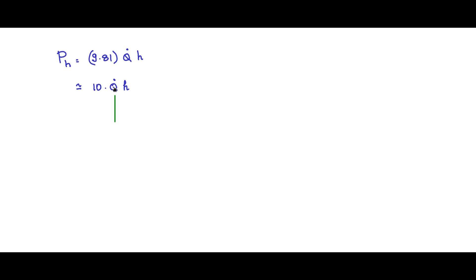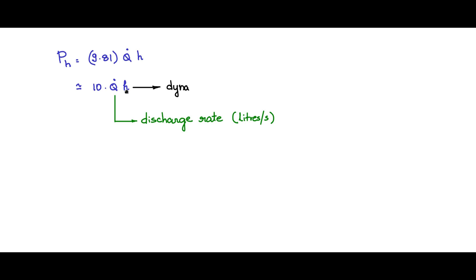The discharge rate or flow rate q̇ is obtained from the application — specifically, how many liters of water you need to transfer from the lower level to the higher level, or how many liters are required for irrigating a given piece of land. This value comes from the user requirement. H is the total dynamic head in meters, which is a combination of the suction head, the discharge or delivery head, and an equivalent head representing friction losses in the pipe. Estimating these heads allows you to calculate the power requirement for the application.